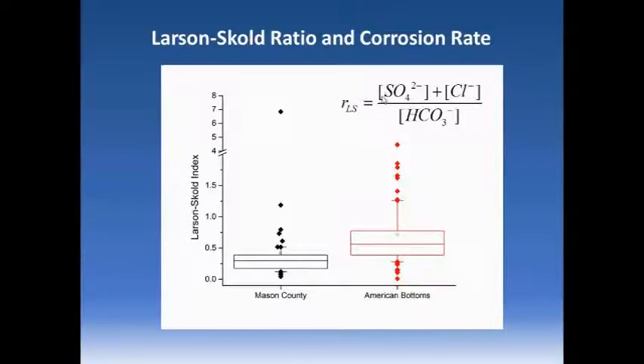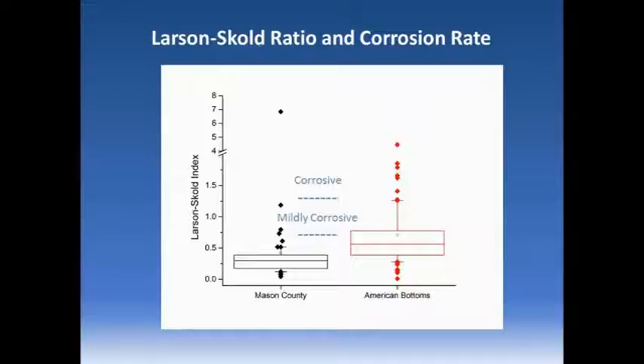They calculated the ratio of sulfate plus chloride to bicarbonate, all in equivalents per liter, and found that for values less than about 0.75 there was hardly any corrosion. Above about 1.3, corrosion became really serious, with intermediate effects for values in between.